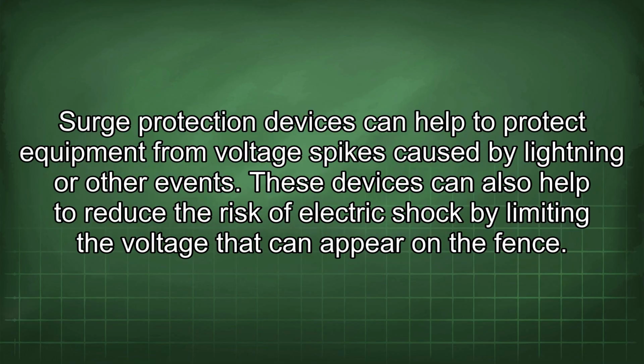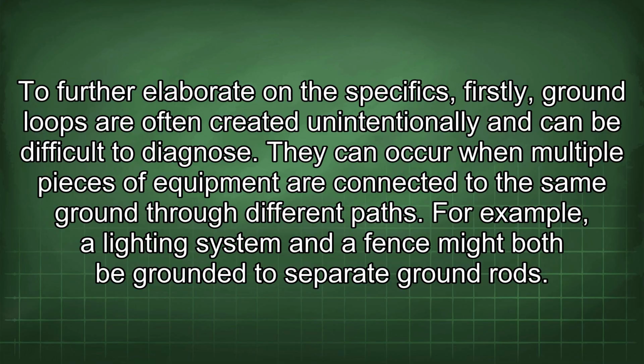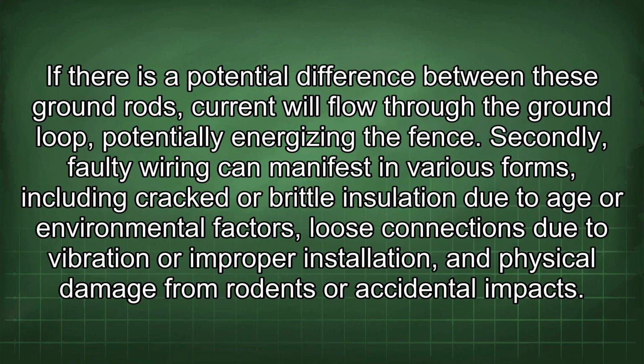Surge protection devices can help to protect equipment from voltage spikes caused by lightning or other events. These devices can also help to reduce the risk of electric shock by limiting the voltage that can appear on the fence. To further elaborate on the specifics, firstly, ground loops are often created unintentionally and can be difficult to diagnose. They can occur when multiple pieces of equipment are connected to the same ground through different paths. For example, a lighting system and a fence might both be grounded to separate ground rods. If there is a potential difference between these ground rods, current will flow through the ground loop, potentially energizing the fence.